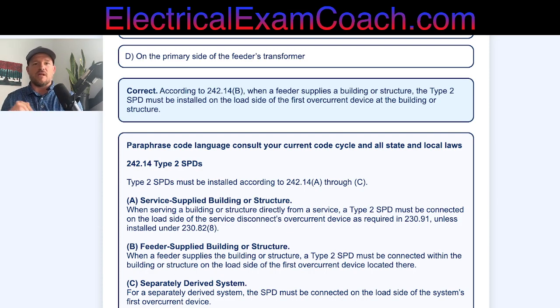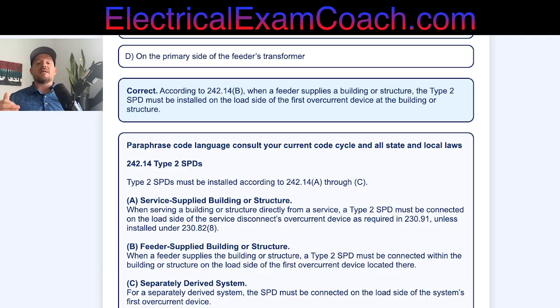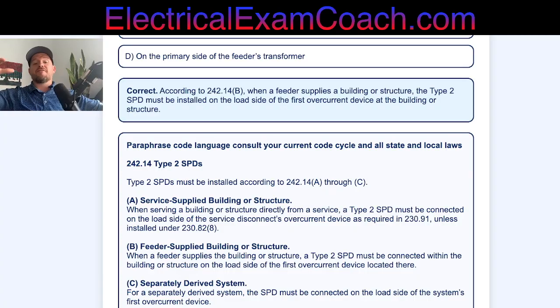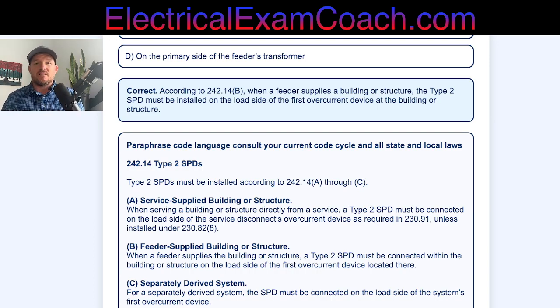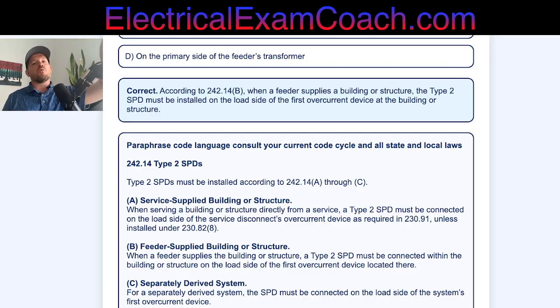Let's take a look at the paraphrase code language — this is out of the NEC 2023. Be sure to consult your copy of the NEC. When we look at the three scenarios, we see that whether the building is supplied by a service, by a feeder like a detached structure, or by a separately derived system, it is required in all three scenarios for the Type 2 SPD to be on the load side of the main overcurrent device. So remember: Type 2 devices go on the load side — wherever your service conductors land at that main breaker or fuse, you're going to be on the load side.